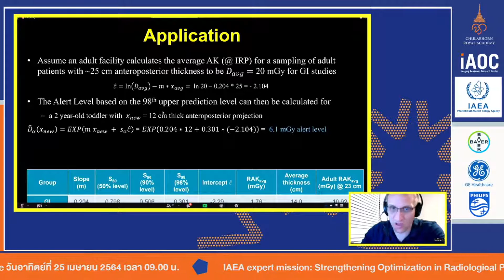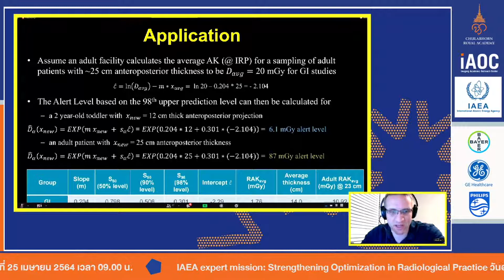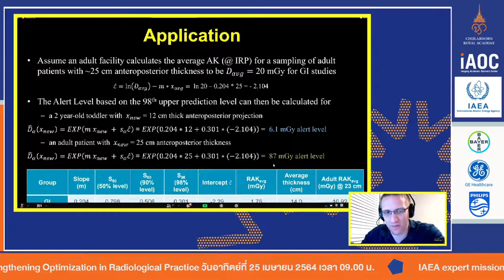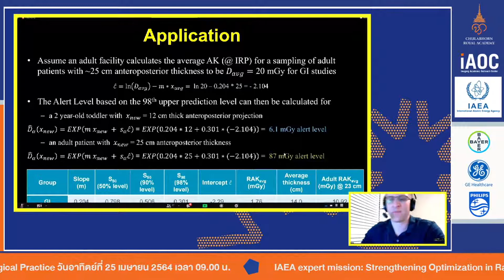So now you could do the same thing for a 25 centimeter patient. If you want to set an alert level, you just do the same thing: get the M slope times the patient's thickness, 25. You're doing it for the 1%, 0.3, and then your scaling factor, which you already calculated. So the alert level now for a 25 centimeter person getting a GI would be 87 milligray. So you can see how the alert levels for non-interventional are going to be a lot lower.